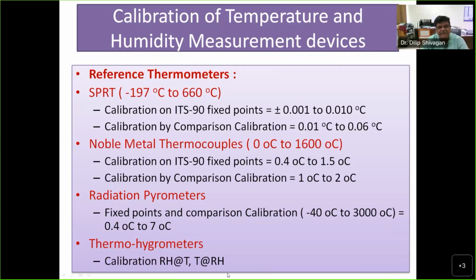For environmental parameters and in many other reference labs also, we have to define RH at a definite temperature, because it is dependent on temperature. And whenever we seek temperature calibration for air temperature also, it should be defined at what RH it is measured. So you need to take care. We have to inform the lab at what temperature you are reading RH and what temperature you are using. If you see the Times of India, yesterday, Friday, it says Delhi feels 52 degrees Celsius. All of this comes from the temperature and RH combination, or thermal comfort, that tourism and other places declare. So it is based on these combinations.